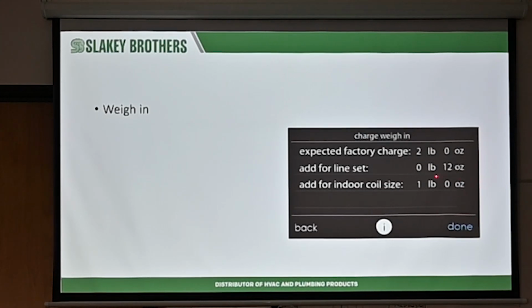So, not everything Bryant gives us is direct. Sometimes you have to be a nerd like me and have a lot of time on your hands to get behind the computer and just read a lot of different stuff for all the manuals, all the different things. And that's where you'll find out that I can't remember what manual, what book it is that Bryant has, but somewhere in there it actually talks about when you match up to certain evap coils, you will add 1 pound or 2 pounds more than whatever the system says, because it's a bigger indoor coil, more efficient, so the system needs more refrigerant overall.